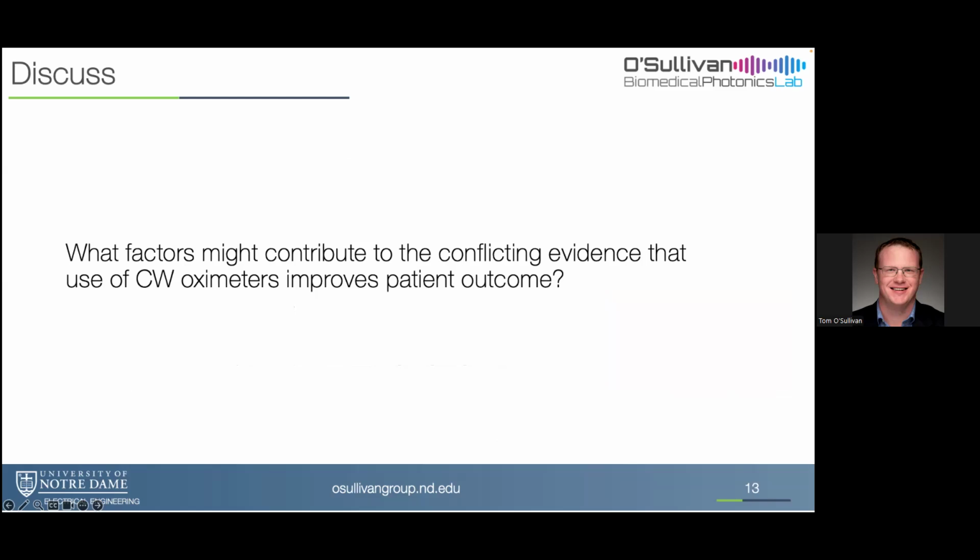You talk about standardization in how they're used, but there's also standardization in how the technology works. What are the source detector separations? What is the underlying algorithm that is correcting for skin pigmentation or correcting for superficial effects? Those algorithms vary from instrument to instrument. And there are papers on this. The folks out of Europe and Switzerland love to publish these papers where they take four different oximeters and put them on the same person, and they get four different readings and four different trends.